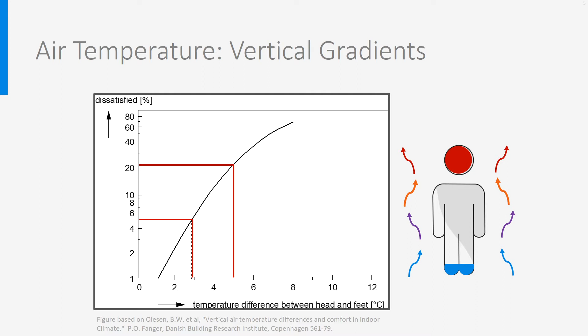Experiments were carried out with people in a state of thermal neutrality, who were exposed to vertical temperature gradients, and there is a relationship between the percentage of people dissatisfied and the temperature difference between head and feet. You see on the x-axis the temperature difference between head and feet. In this graphic, the head temperature is always higher than the one of the feet. The opposite would not create discomfort. For instance, if the temperature at head level is higher by almost 3 degrees Celsius than the temperature at ground level, this will lead to 5% of people dissatisfied. If the temperature difference is 5 degrees, the percentage of dissatisfied increases enormously and is around 24%. So, in case of comfort complaints, this is certainly a parameter to measure.